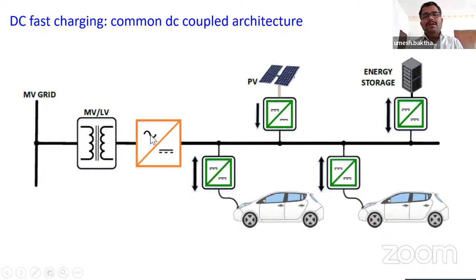Here, it's a centralized inverter rated for all the DC-DC converters combined. The sum of the power consumed by these individual DC-DC converters should be managed, or the inverter should be rated to handle that total power.